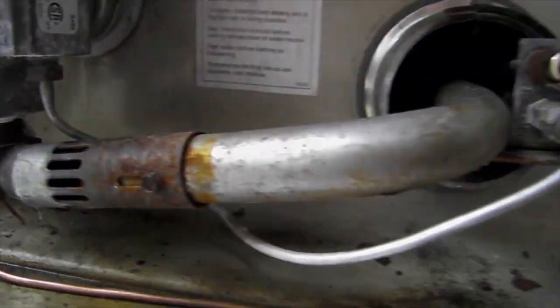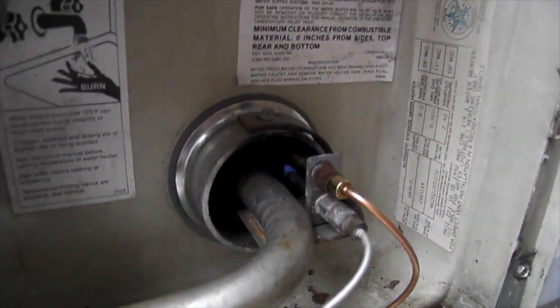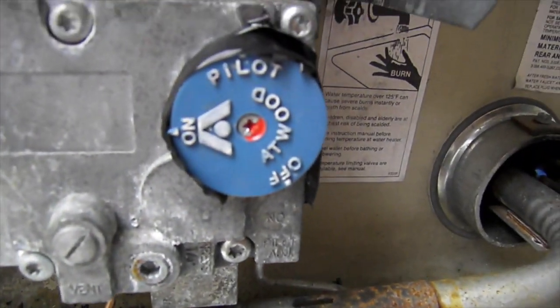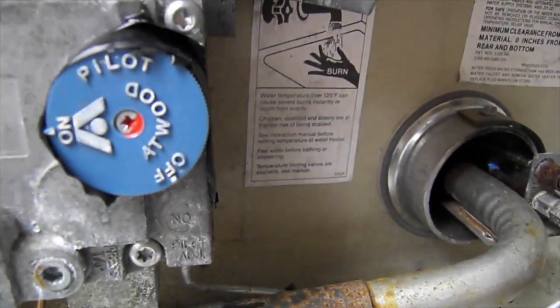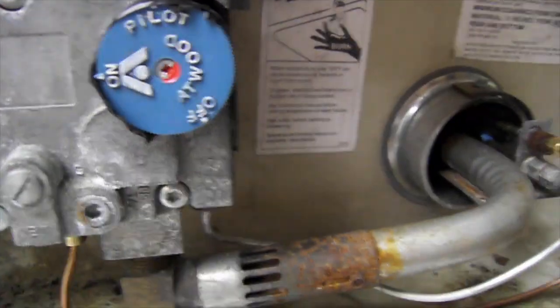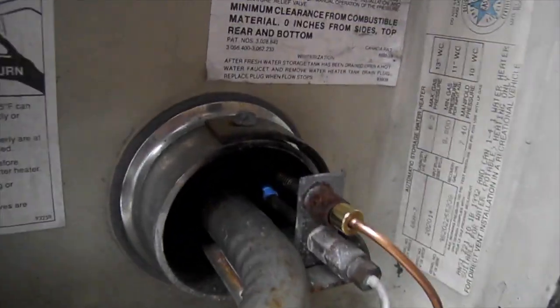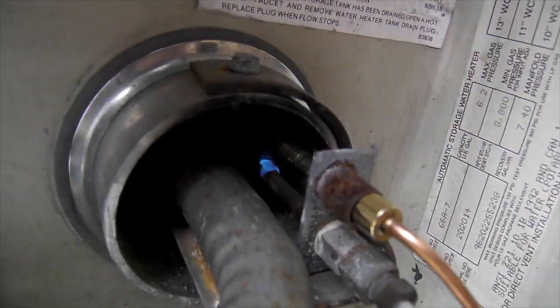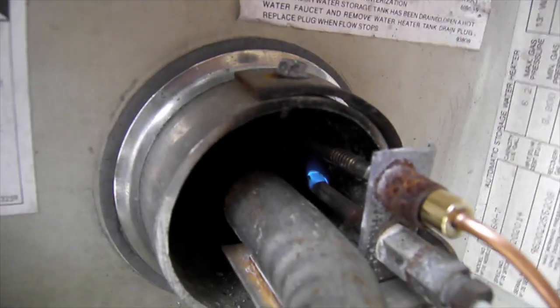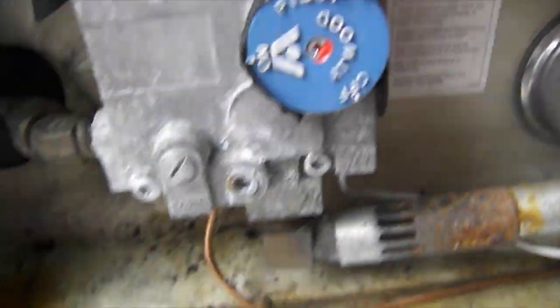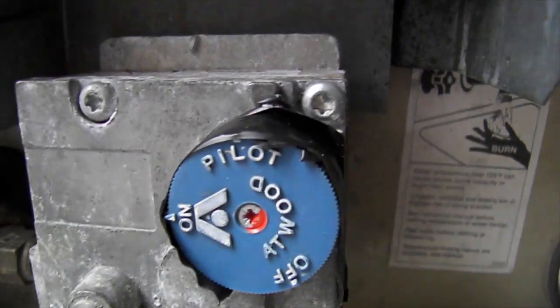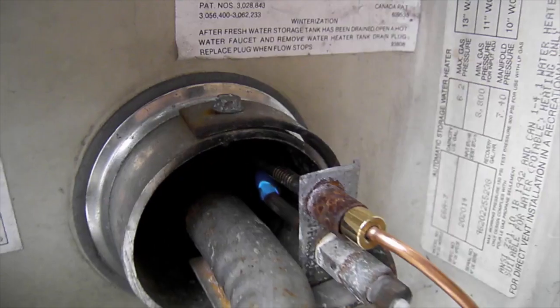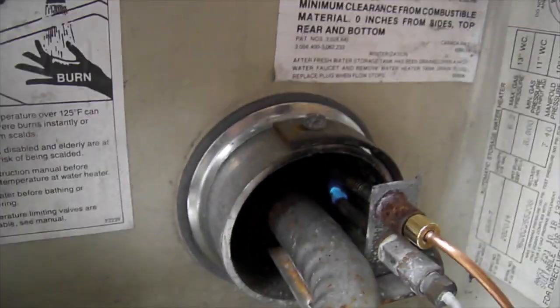Okay, after about 15 minutes of trying to hold this pilot knob in the pilot position, which is what you got to do, takes a while for the gas once you turn it on up front to get all the way back here. But this pilot light is staying lit, it's nice and healthy as you can see there. I got tired of holding it, so I took some tape and held it there. I'm going to let that pilot light run for a little bit and we're going to see if this whole thing will work now.